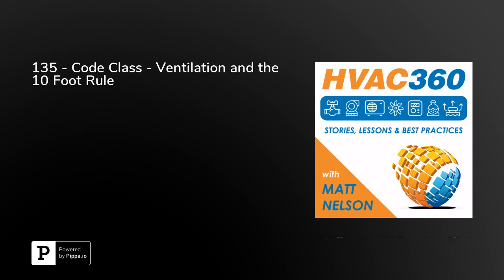All right. So now we get to step 3. Step 3 actually has a bunch of what we're talking about because it says for all environmental exhaust. Okay, that's pretty all-inclusive. You have to be 3 feet from a property line, 3 feet above an operable window. Again, that's the same thing that we heard about before. And it needs to be 10 feet from any mechanical fresh air intake. Okay, that's fine. Such exhaust systems shall not be considered hazardous or noxious. So when they put these guidelines in for 3 feet, 3 feet, 10 feet, again, they're not hazardous, they're not noxious.